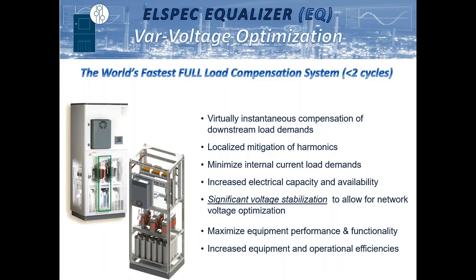pure electronic switching. So all of our systems have no electromechanical parts or contactors. Basically, the way the system works is it will monitor and calculate the full load demand response required on that network in less than a quarter of a cycle. And then it will wait for the voltage waveform to actually cross the zero threshold, and it will engage each phase as the voltage crosses that zero potential.